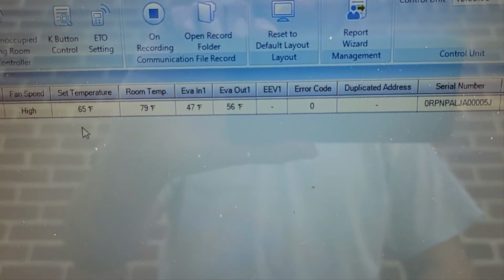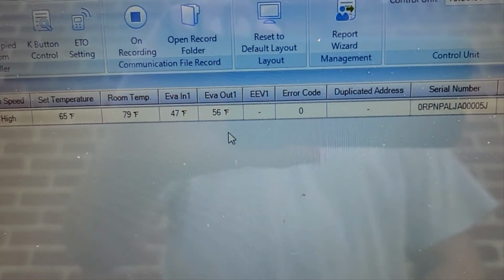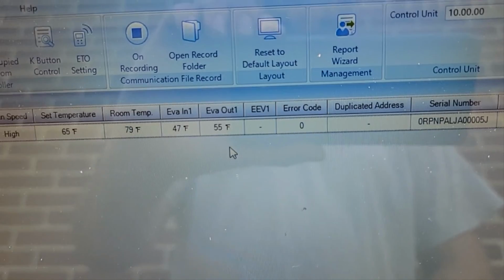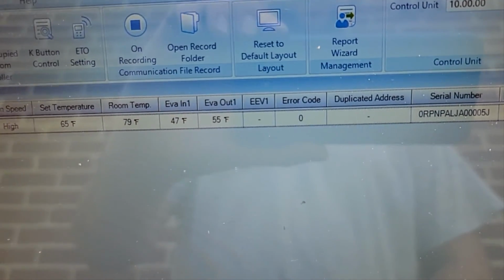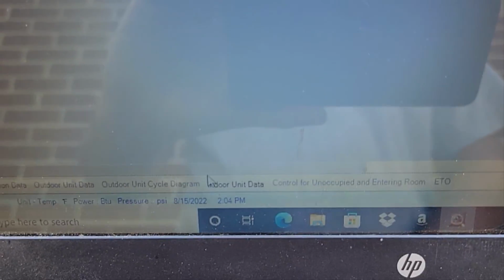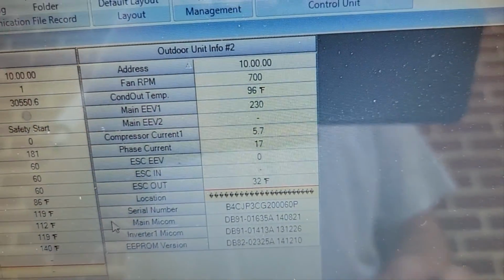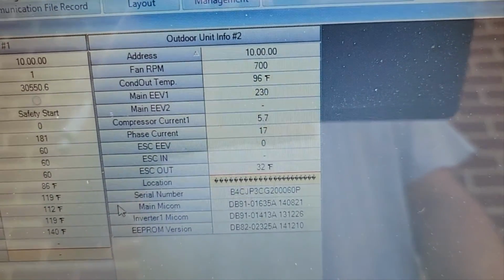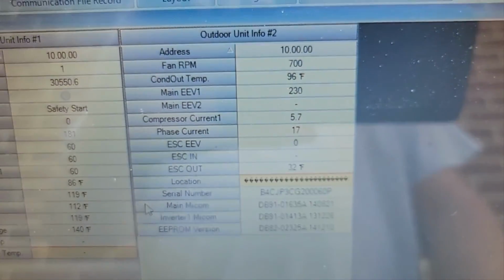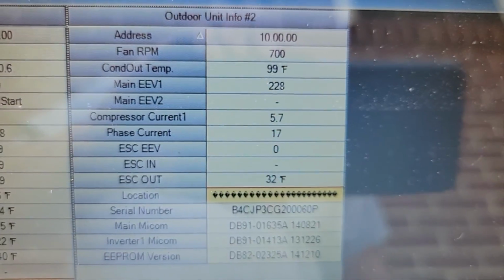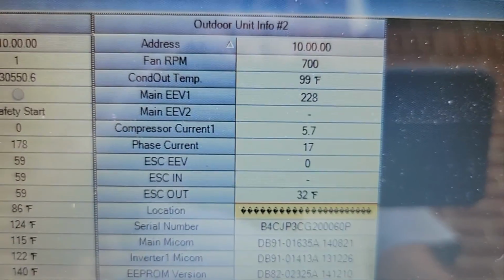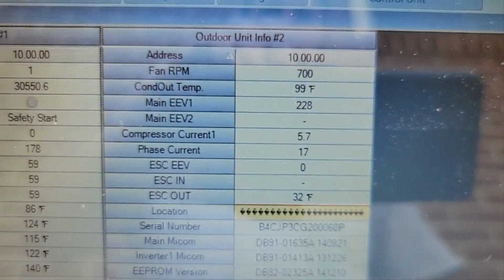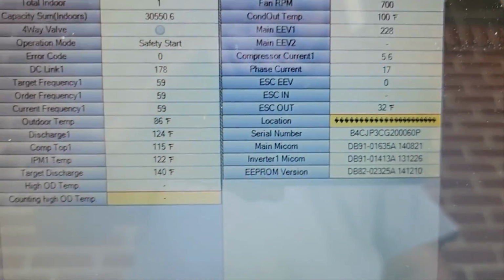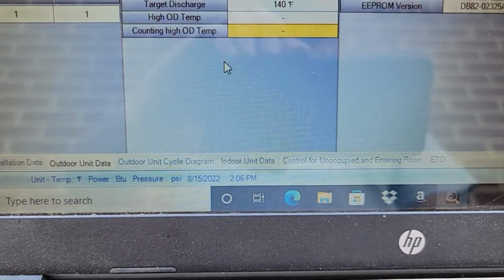Indoor unit data, evaporator inlet is 47, evaporator outlet is 55, got some temperature difference. Very good. Go back down, outdoor unit data, EEV is now 230. Beautiful. About a minute later, EEV 228, so it was 230, now it's 228.